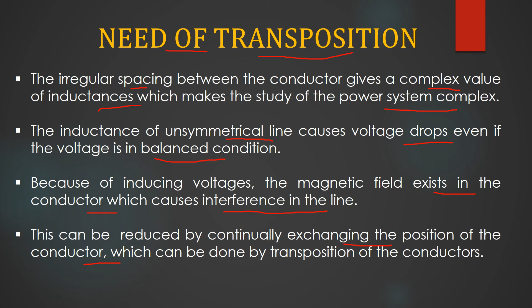To reduce this induced voltage and the magnetic field generated, which causes interference in the line, we have to make the conductors equally spaced and continuously exchange the position of each other, and this exchanging of position with respect to each conductor is called transposition.